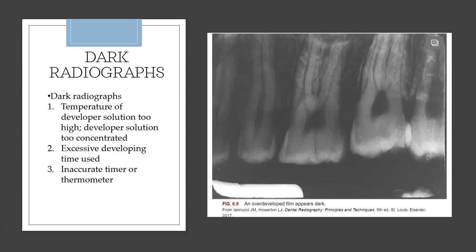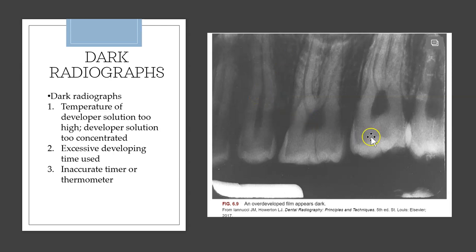A dark radiograph is an overdeveloped film. This can happen if the developer solution temperature is too high or if the development time was too long. We see this less now because digital radiography has largely replaced traditional darkroom processing.